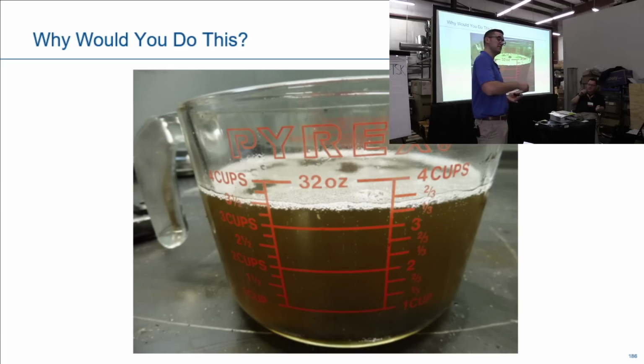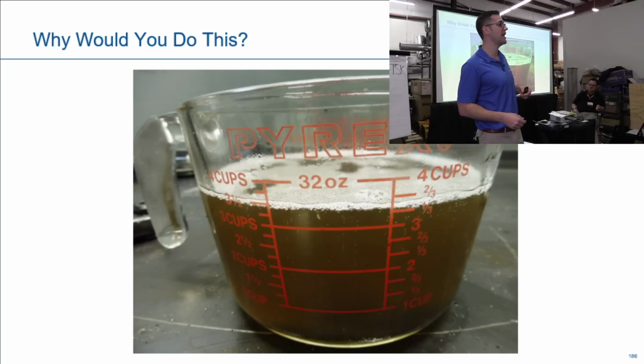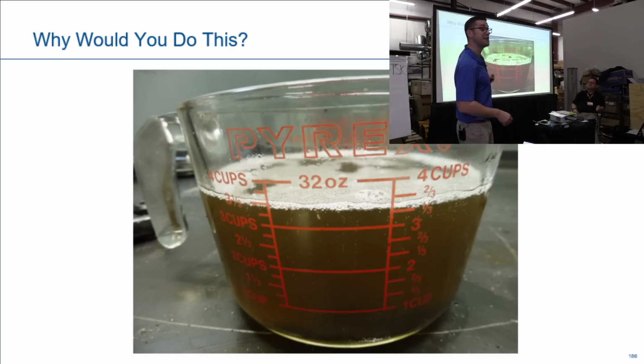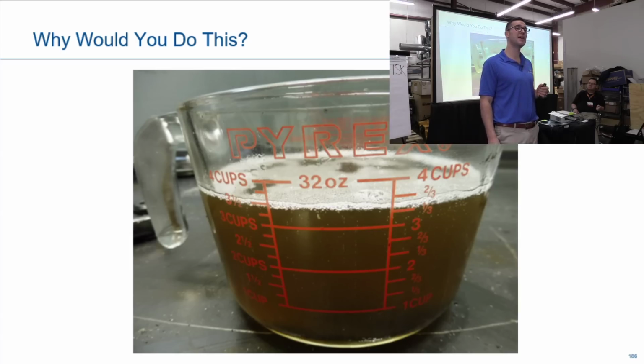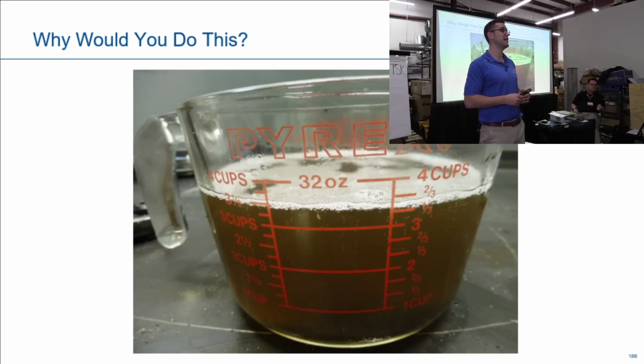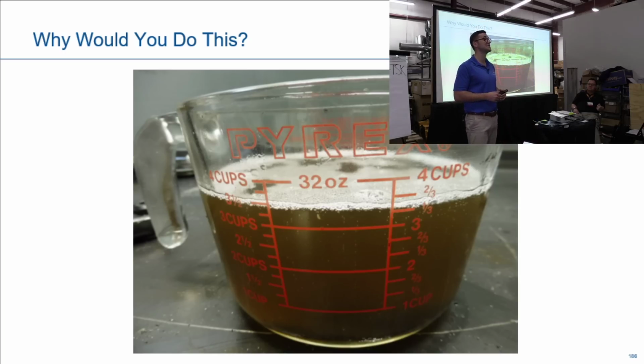So I write down it, 46 ounces. So I get my measuring cup in our lab, Copeland Lab, pour it in, and this cup here, 32 ounces. Almost 32 ounces. The compressor said 46. I had over 90 ounces in the compressor. That's an issue. And that was 90. And it was supposed to be 46.